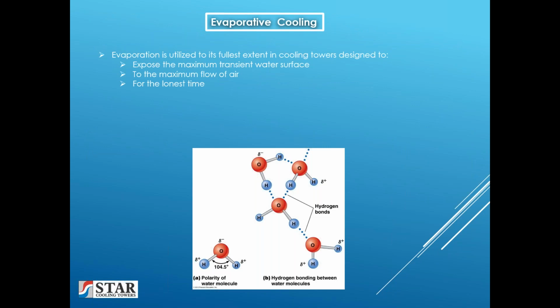Evaporation is utilized to its fullest extent in a cooling tower designed to expose the maximum transient water surface to the maximum flow of air for the longest time. This highlights an aspect of cooling tower performance that those in the industry would not typically recognize, that 70 to 90% of cooling is due to evaporation of a small amount of the water to be cooled.